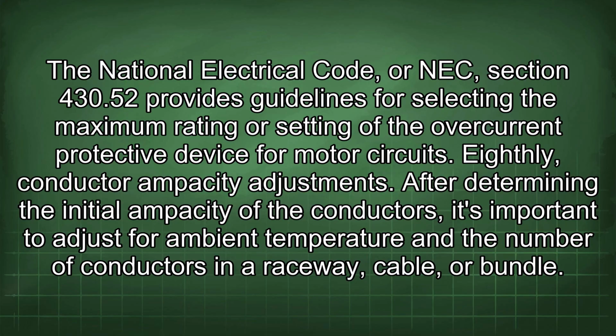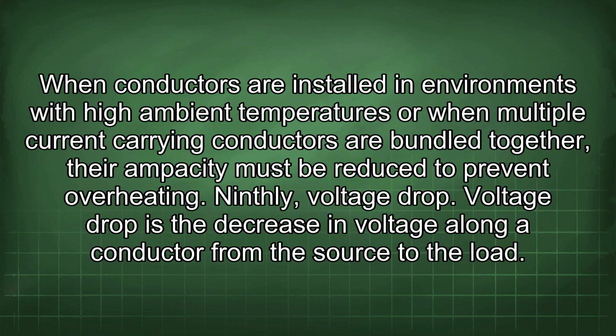Eighthly, conductor ampacity adjustments. After determining the initial ampacity of the conductors, it's important to adjust for ambient temperature and the number of conductors in a raceway, cable, or bundle. When conductors are installed in environments with high ambient temperatures or when multiple current-carrying conductors are bundled together, their ampacity must be reduced to prevent overheating. Ninthly, voltage drop. Voltage drop is the decrease in voltage along a conductor from the source to the load.